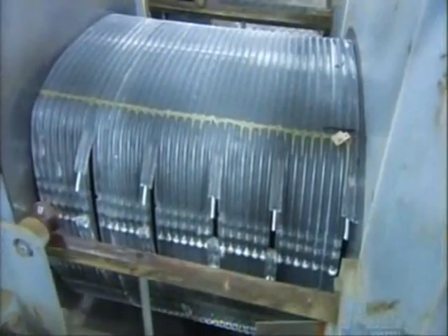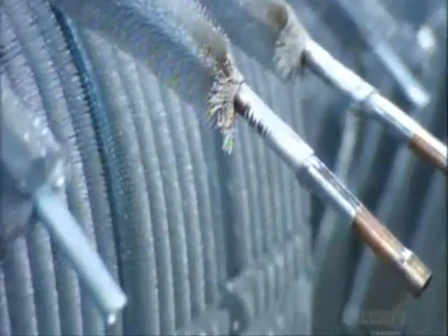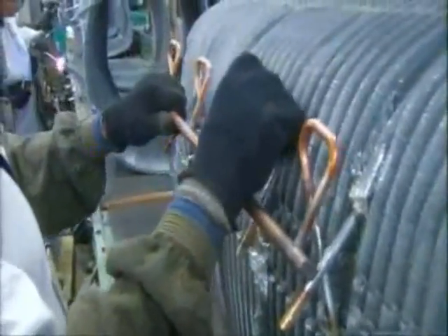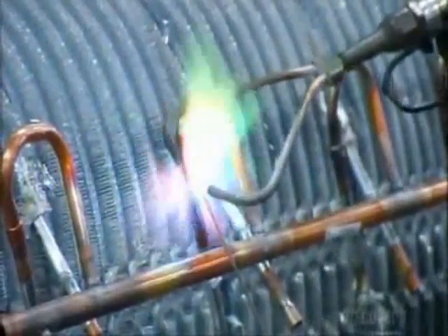The pipes that feed these circuits are made of copper, but copper doesn't fuse directly to aluminum. So workers must first solder on transition tubes coated with a zinc aluminum alloy, then attach the copper manifolds that distribute the refrigerant to the circuits.